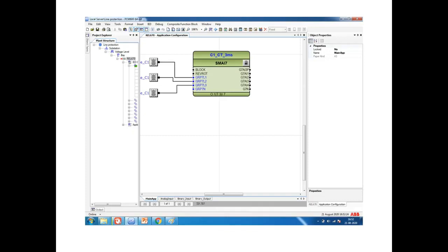signal. So after connecting this signal, this block has another function, the output of the block. If you see the 3P, that is RYB, the 3-phase current we can get at a single point. When you see below that, AI1 will give output correspondingly L1. Similarly L2 will give I2, L3 will give I3, N will give I4.